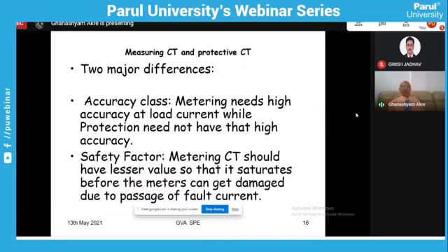The two major differences between the measuring and protection. As I told you, the main purposes of the current transformer are, one, the measurement of energy or power, and second, the protection of the total system. So the major differences are the accuracy classes and the safety factor. In a current transformer of metering type, it needs high accuracy at load currents, while protection need not have high accuracy.